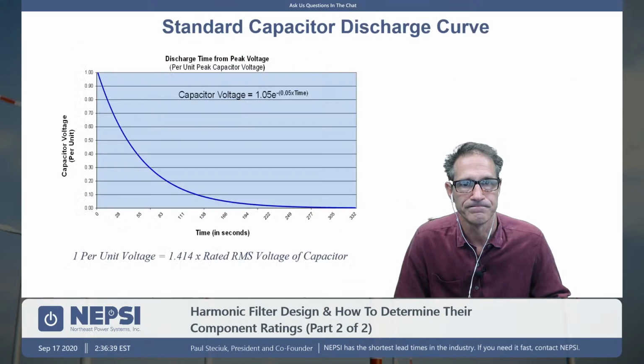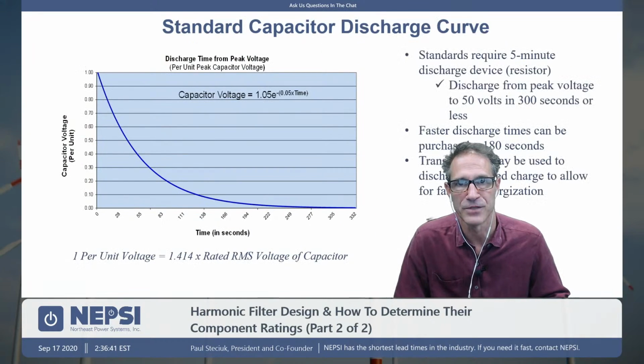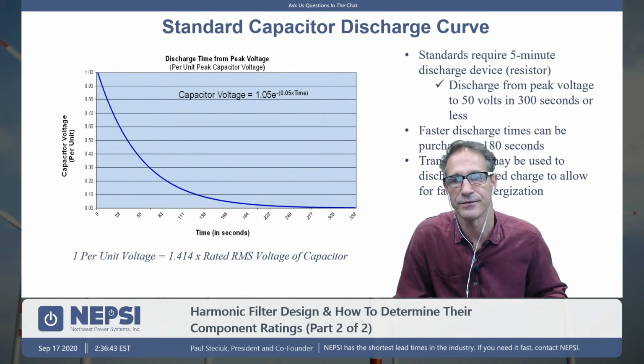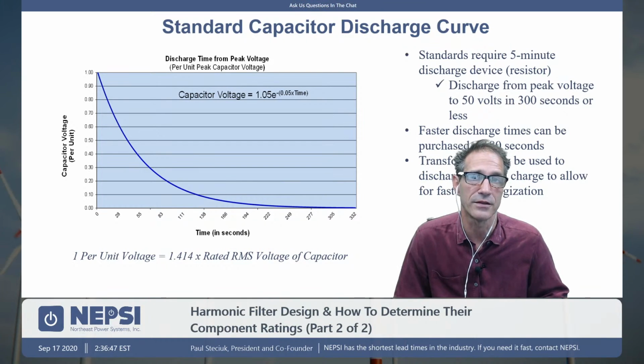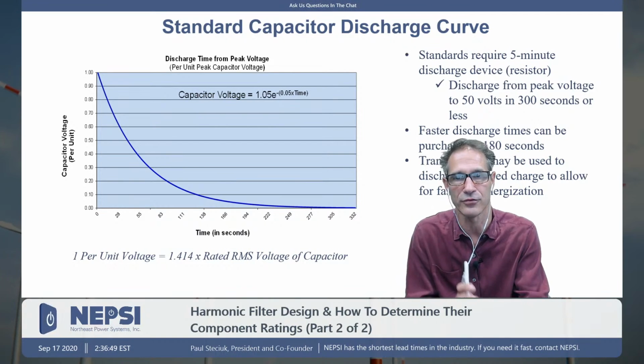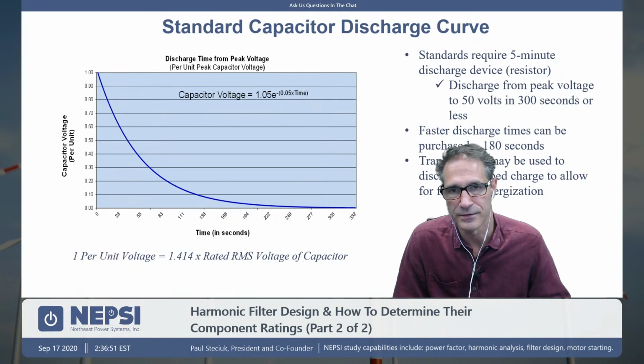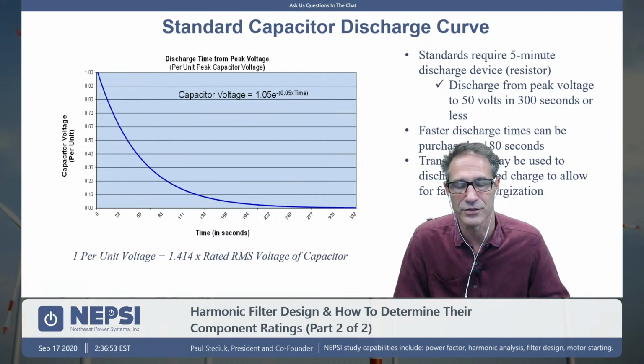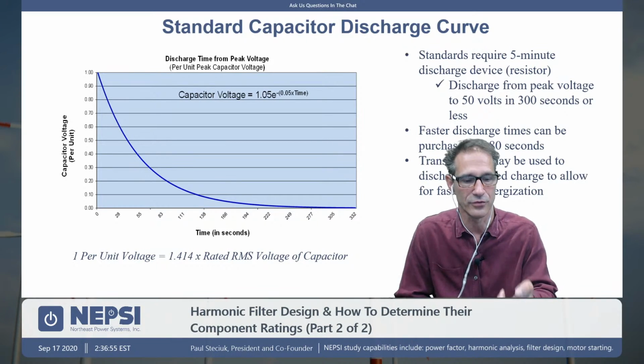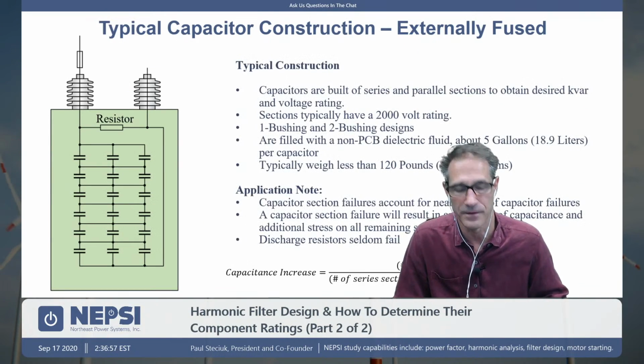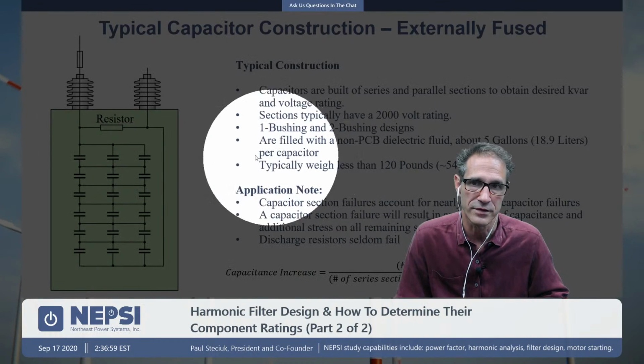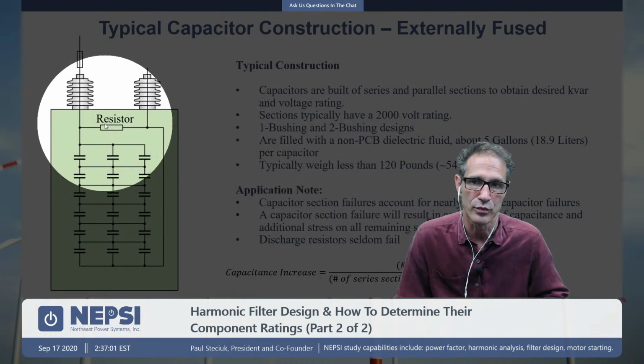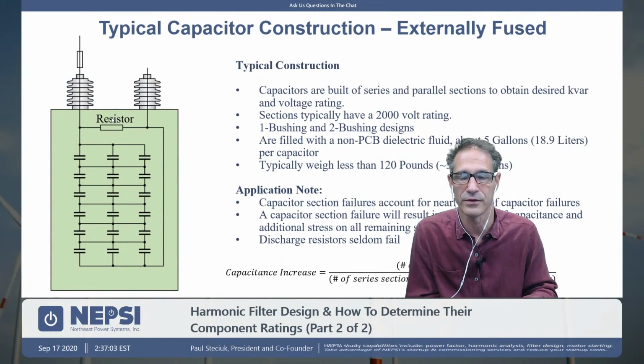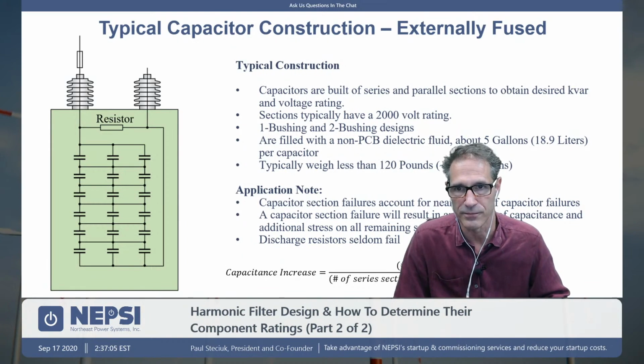All right. They have capacitors in North America. The IEEE standard, basically the CSA standard, both dictate that your capacitors will discharge in 5 minutes. So there's a discharge curve associated with it. They insert that resistor inside the capacitor itself, like you see here. And when you de-energize the equipment, it will take 5 minutes for the capacitor to discharge. So that's what we show here.